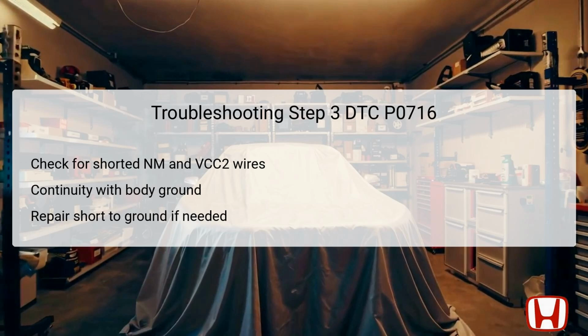If continuity is found, it confirms a short to ground scenario, necessitating repairs to the wiring involved. If no continuity is present, it indicates that the NM and VCC2 wires are likely functioning correctly, and attention should shift to the sensor unit for potential replacement.